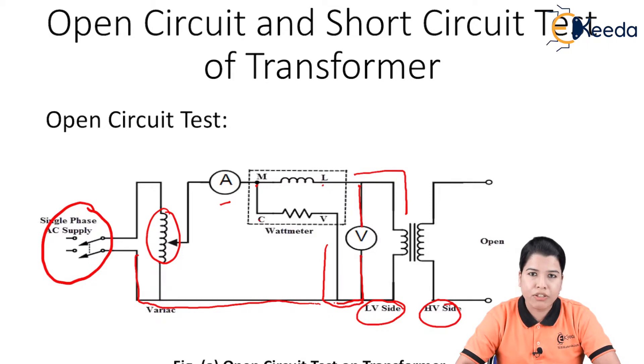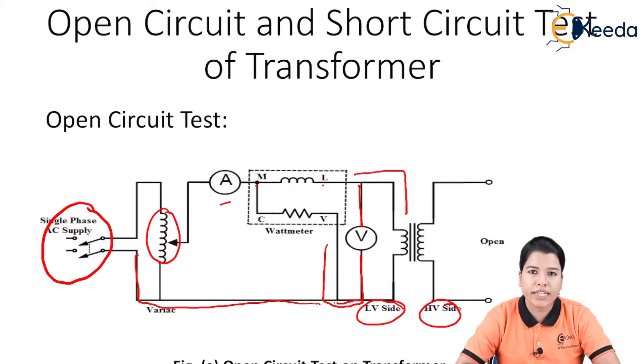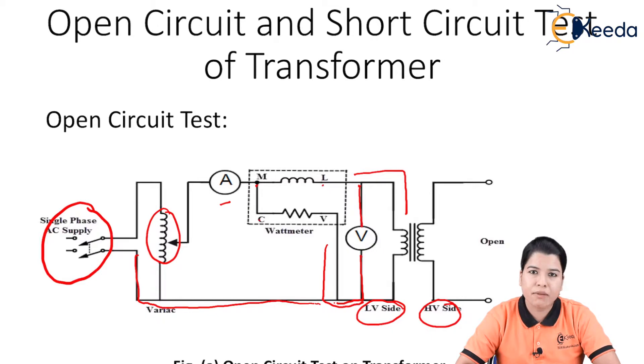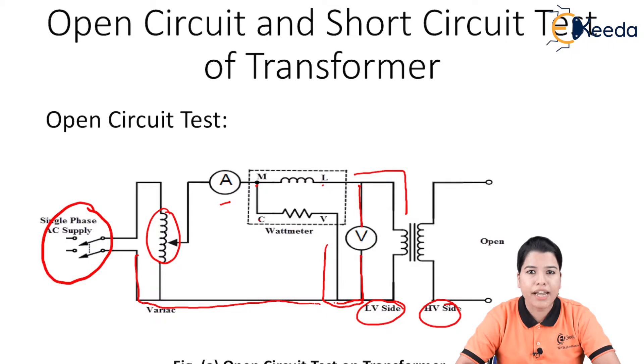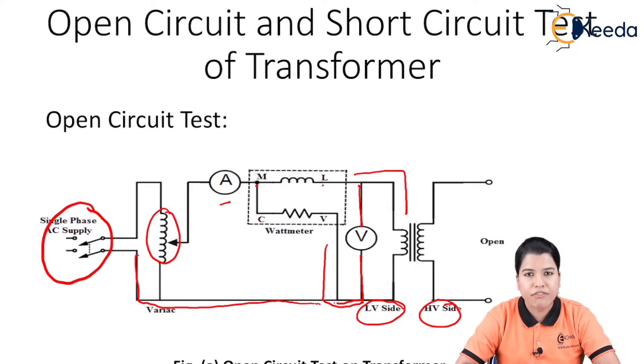When rated voltage is supplied to the primary winding, the secondary is open circuited, so a very small no-load current I0 flows through the ammeter. This no-load current is nearly 2% to 5% of the full-load rated primary current. Since the current is very low, the copper loss is negligible and can be neglected. Therefore, the wattmeter W will record only the iron losses.